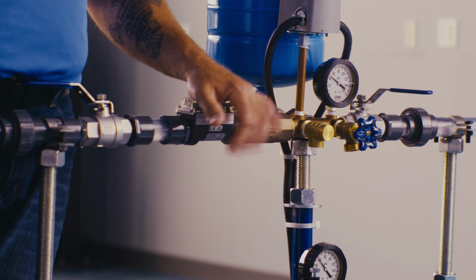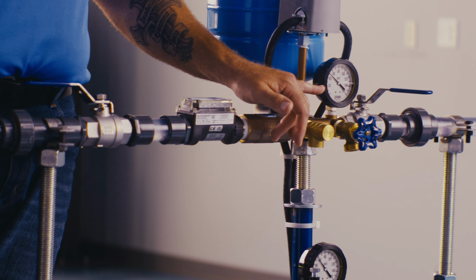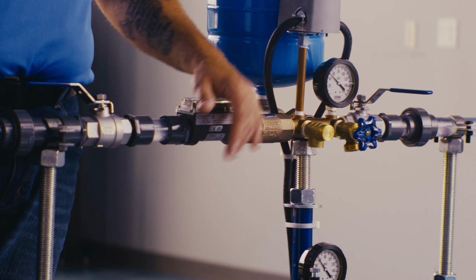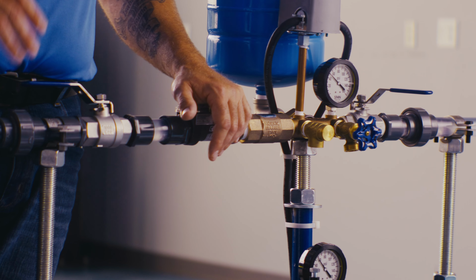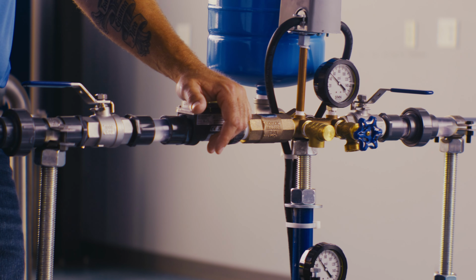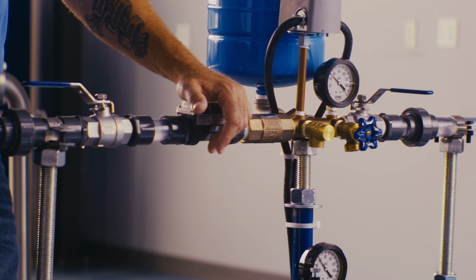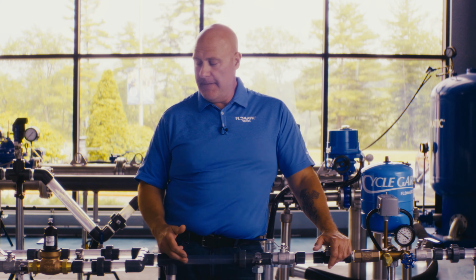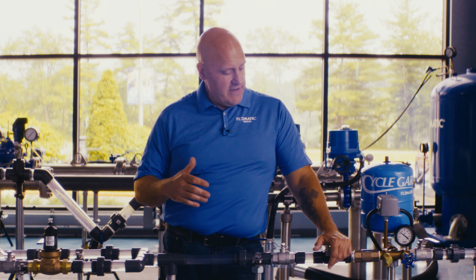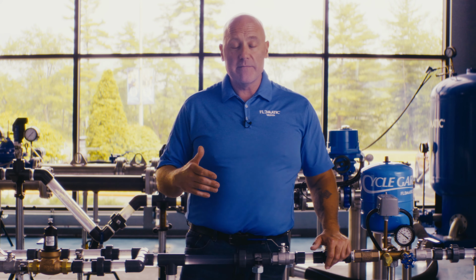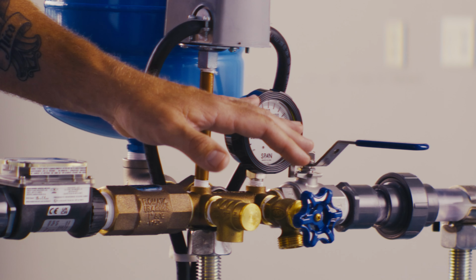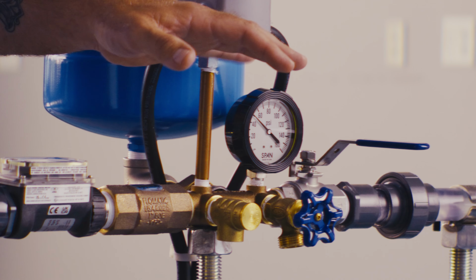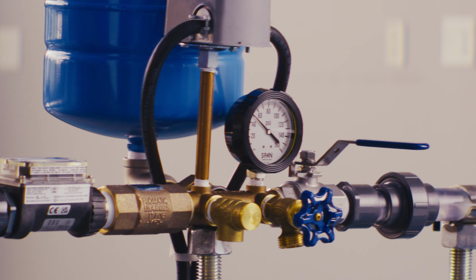So our pump just started. You'll notice the pressure build to approximately 50 PSI, and it's going to stay steady. Our pump is now not starting and stopping. This is going to protect the pump. Electric motors like to run. They don't like to start and stop. So it's going to keep us within our recommended starts per motor manufacturer, lower our amp draw on the pump itself, on the motor itself, and it's going to allow a nice steady system pressure of 50 PSI.